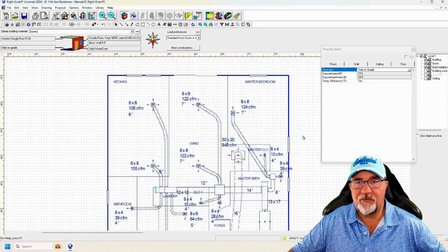So when you're designing a duct system, let's say this is a flex duct system, which is typically what's installed in Florida. You can't get away from it much. This here would be the rigid fiberglass duct that comes off, and then we would branch out with the flex duct into branch boxes or whatnot. The issue we run into, and I know this from being taught years ago, is when we size that room and say, okay, that room's 127 square foot, we're going to put 127 CFMs in there. Then all of a sudden we have these rulers in the field that tell us that 127 CFMs is a 7-inch duct. They call it a ductulator, and there are other tools.